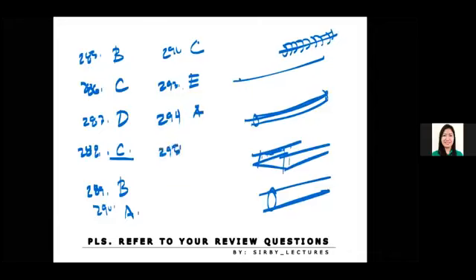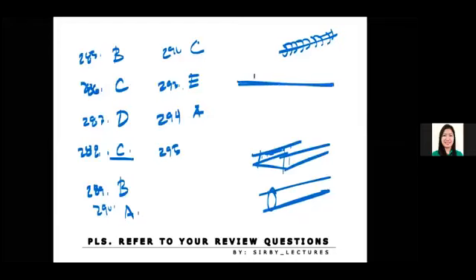295. A 15 mm rigid metal conduit is used for the wirings of a bag storage warehouse. The conduit is supported by a series of steel clamps spaced at a distance. What is the maximum spacing allowable? What this means is that we have this wire inside a conduit, and it is being supported by clamps, and the question asks what is the maximum distance between clamps?